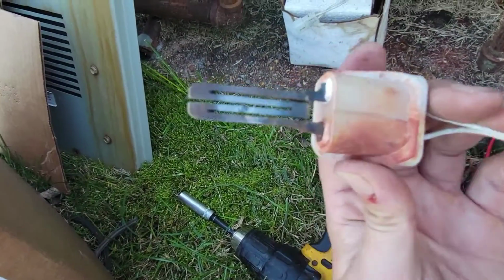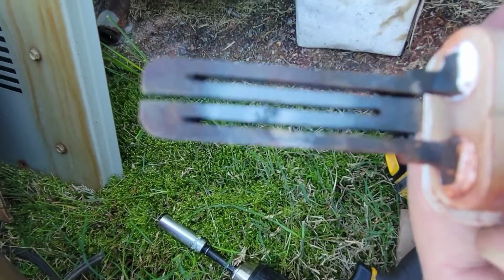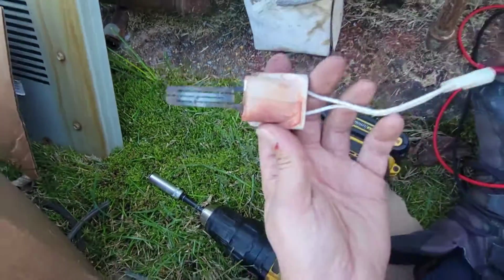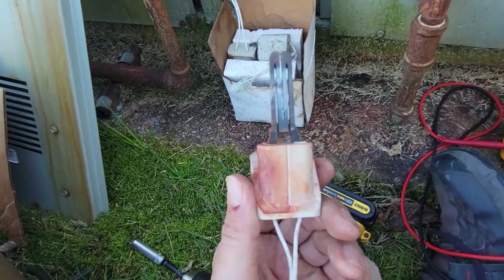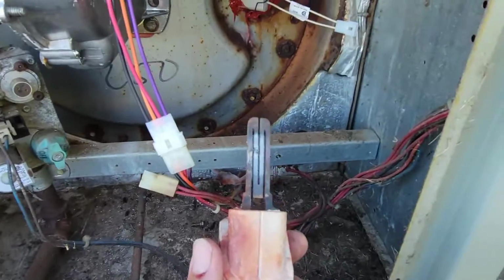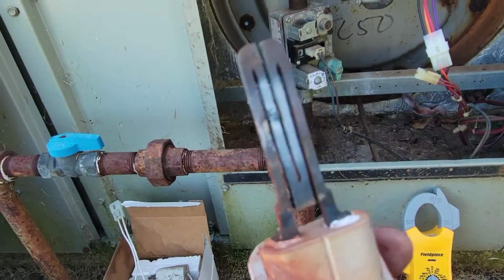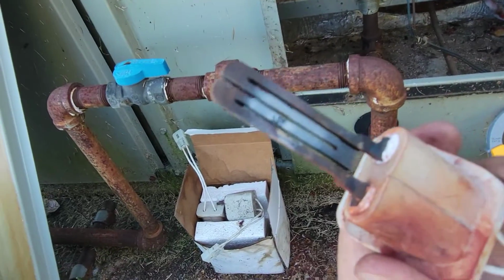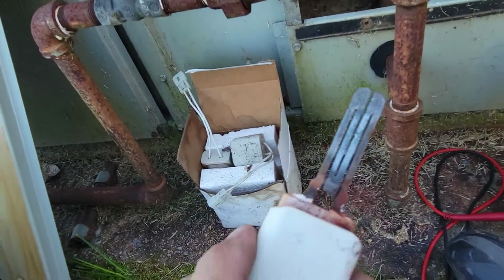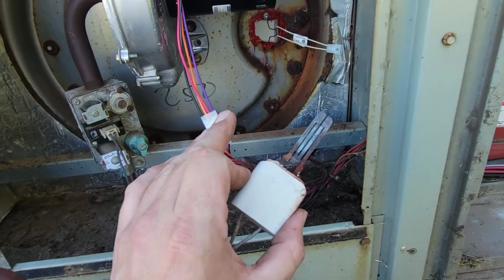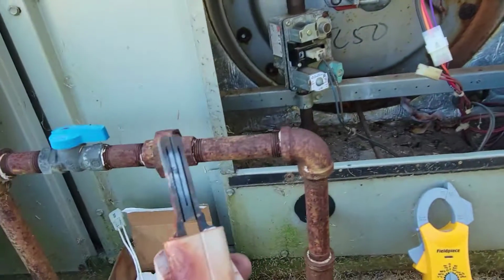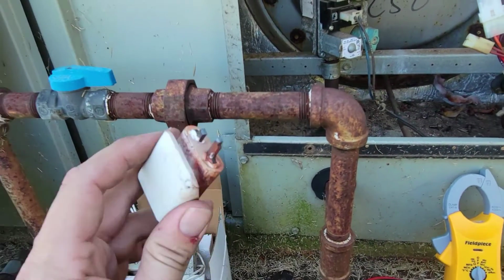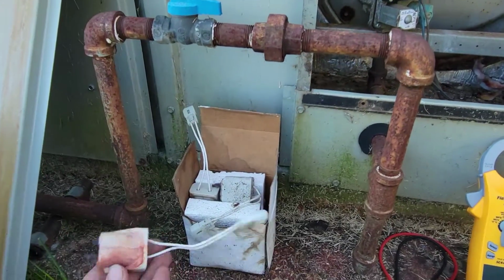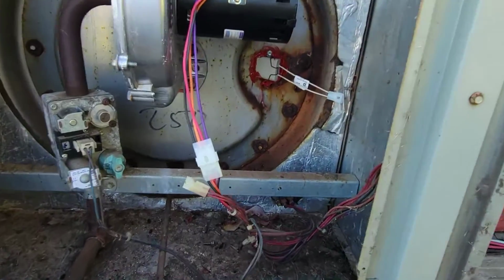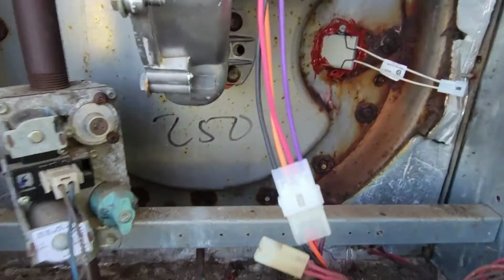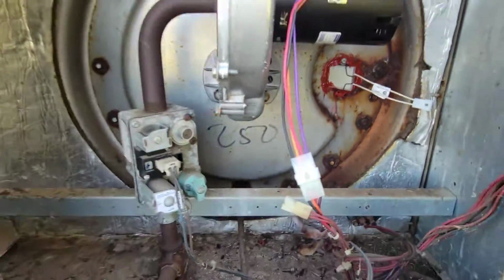I'll show you the crack when I take the power loose from the hot surface igniter. This right here is the bad hot surface igniter. That little area right there is the part that's damaged. That's what's keeping this from operating properly. We've got a new hot surface igniter now, and it doesn't have this white spot and it doesn't have this crack. These are easily damaged, by the way. Be very careful when you install a hot surface igniter. If you touch this, it'll break so easily. So let's plug in the new hot surface igniter and watch the glow.